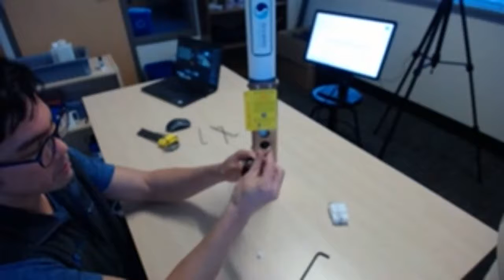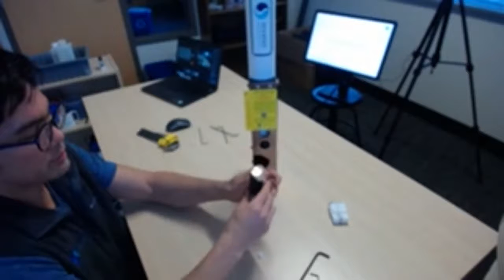Okay, so removing that helps to prevent any of this solution from contacting the pins on the connector when you take it out. If you're careful, you don't necessarily have to do that every time, but I would recommend doing it. It's a very tiny amount of solution, so you're not really wasting that much. And then I'm going to loosen the 2 screws on the pH sensor a little bit at a time, until they are no longer connected to the soaker block. I'm going to put this down and pull this straight up. Pulling it straight up prevents any of the solution that's inside of the reservoir from spilling over to the connector.